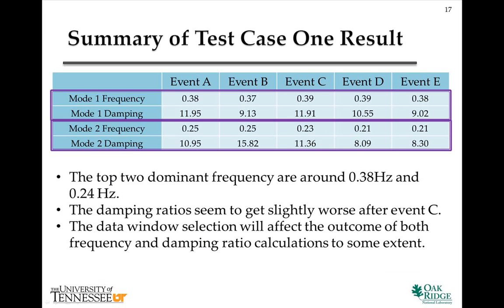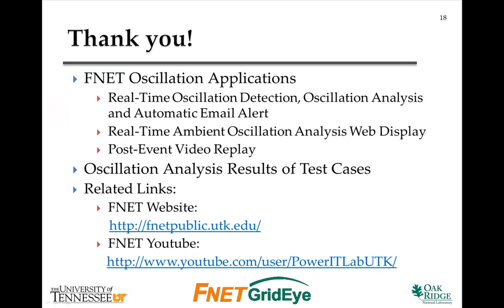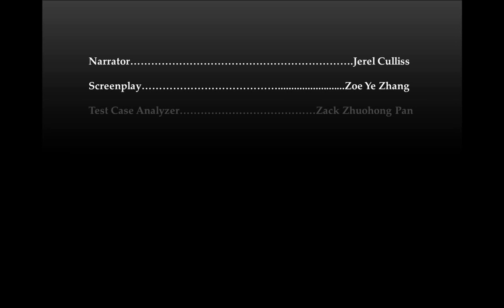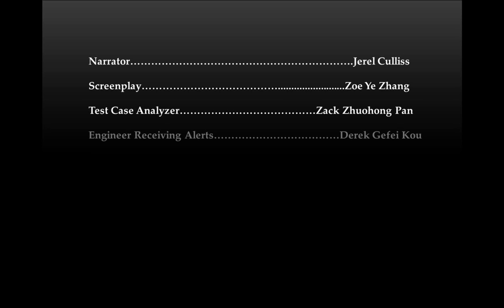In conclusion, our video provides analysis results of oscillation test case 1. The two dominant frequencies for the five events are around 0.38 Hz and 0.24 Hz. The damping ratios seem to be lower after event C. In this video, we introduced several oscillation applications. You are welcome to check out more information on our website and YouTube channel.